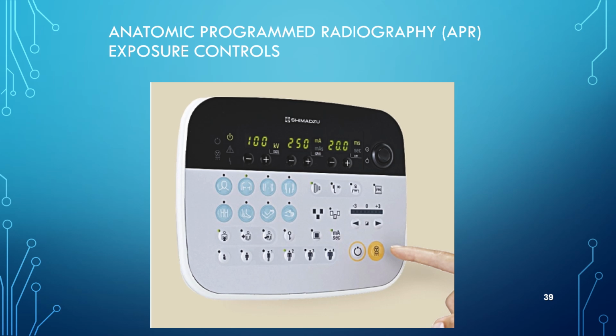Now sometimes this looks a little bit older. Sometimes it's a touch screen system where you select chest and then it says ribs, chest PA, chest lateral, and so on and so forth. And then you keep getting more specific with your selections, and then it ultimately recommends a technique to you. That's what I'm used to. The Canon selection menu is like that. So is the GE selection menu. Okay, and so that's your APR. Your APR basically has taken the place of paper technique charts.